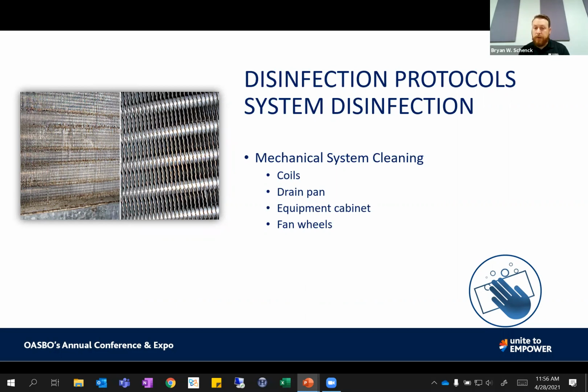So you want to look at cleaning your coils, your drain pans, the cabinet of the equipment, and your fan wheels. Dust builds up on those, just like it builds up on the fans in our homes. It can build up on the fan wheels within our mechanical equipment, which are the main means of moving air within our mechanical system. So it's very important to look at that in your cleaning protocol as well.